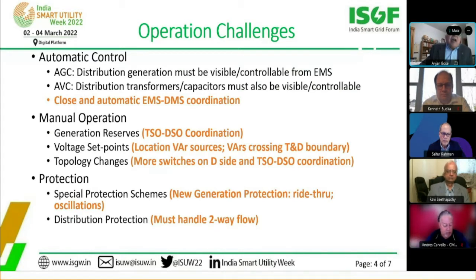But that's not going to be the case once a whole bunch of generation moves into the distribution side. So now the EMS operator, or the EMS itself, will have to send generation signals to the distribution side, which means there has to be much tighter control and coordination between the EMS and the DMS.